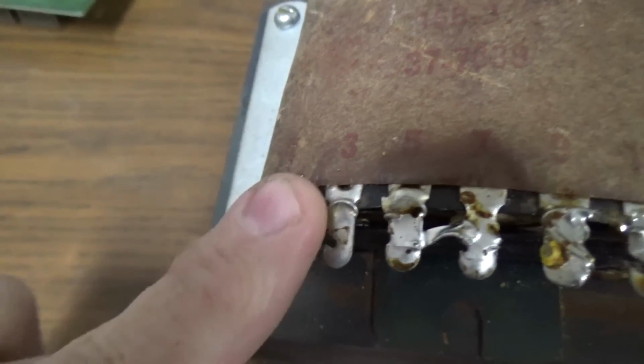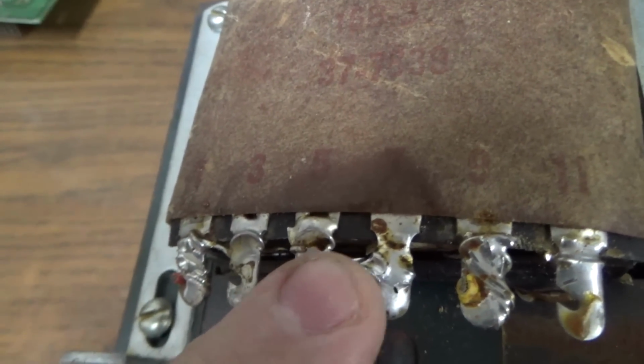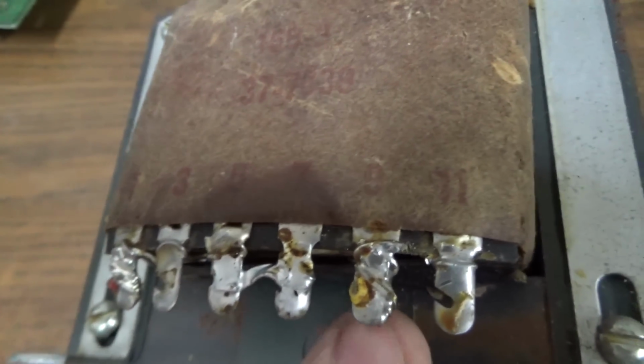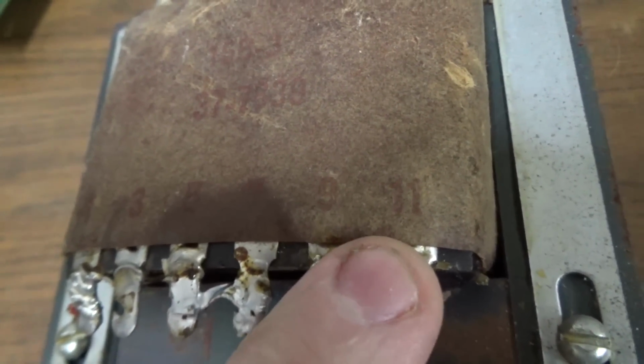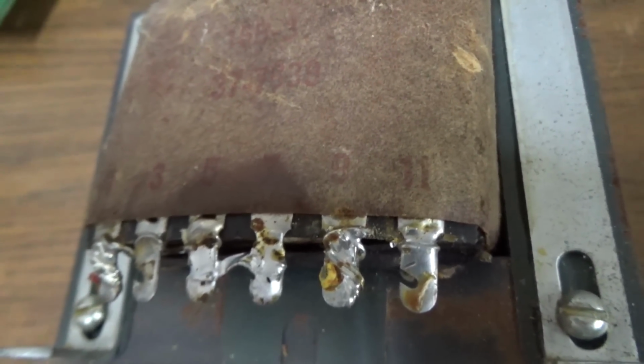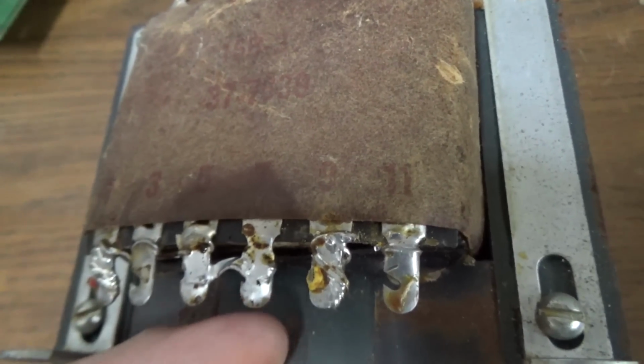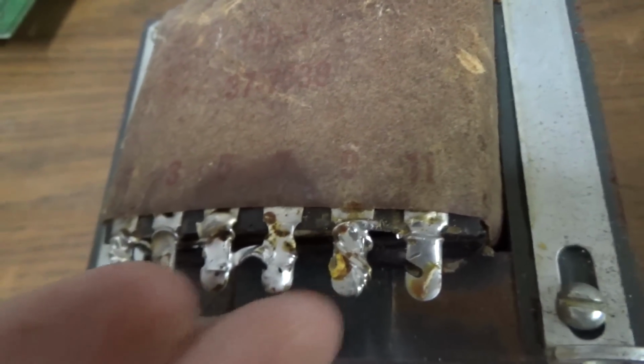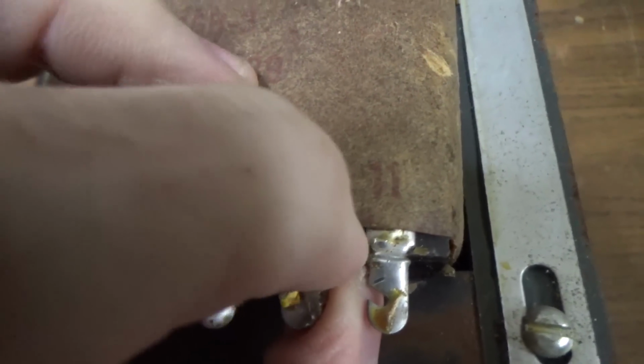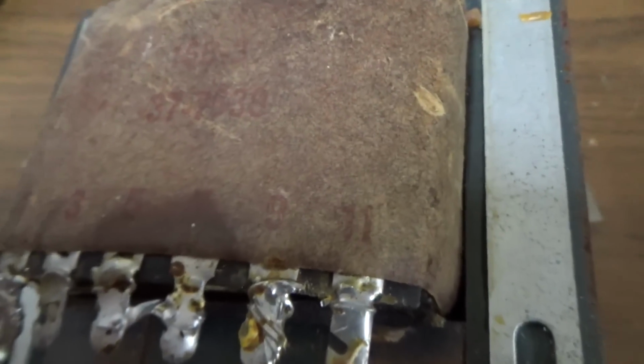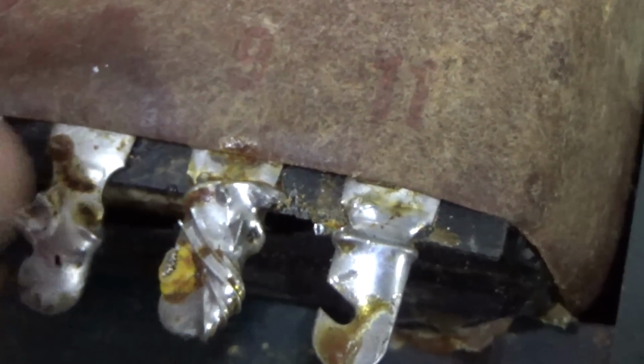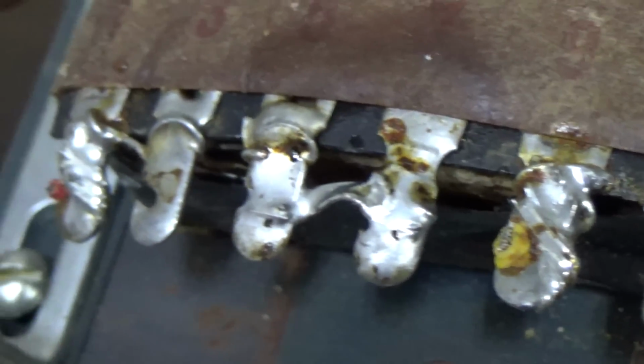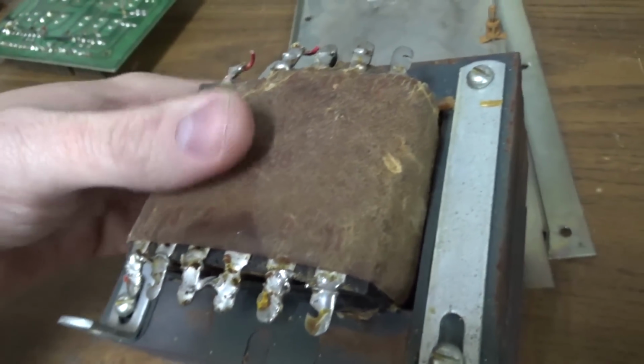So 1 and 3 is still connected—I didn't do that. I added a jumper to 5 and 7, and then I removed the jumper from 9 and 11 because we're not using it. It probably doesn't matter if you leave it hooked up, but it might, so I don't. There was a strong wire connecting those together, and I've cut it loose, so this one does not touch this one now. Okay, so that's good.